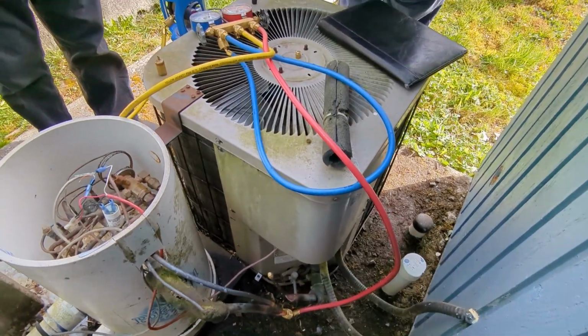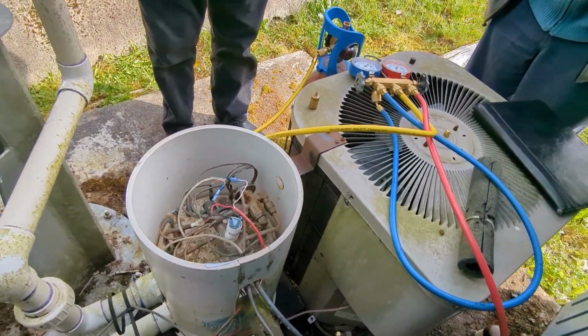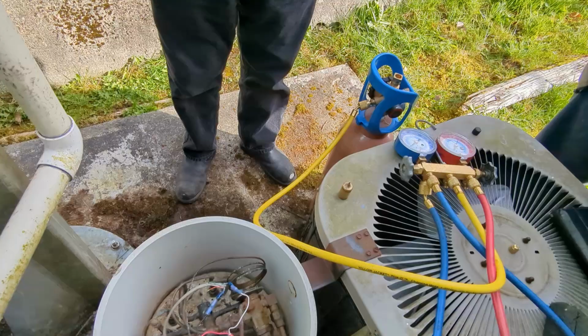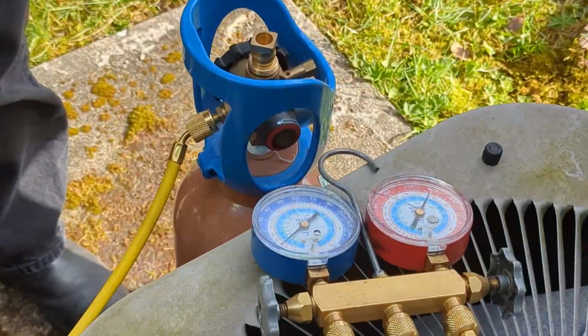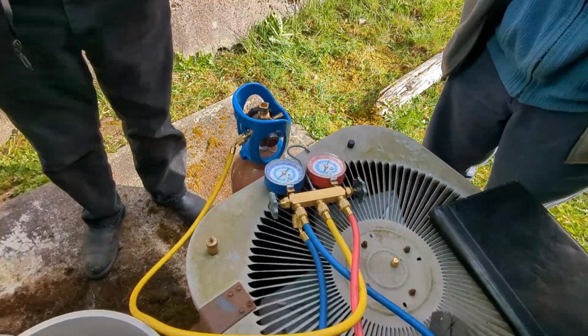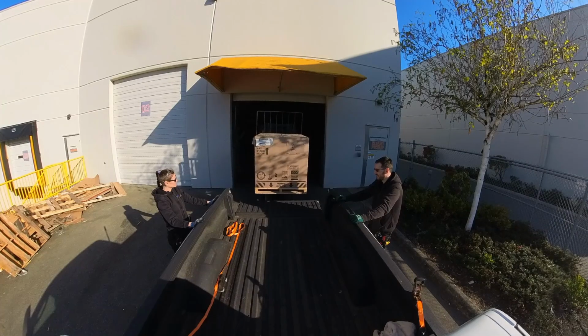All right, we got our nitrogen back out, and we've pressurized this guy back up to 300 psi, and we're gonna leave her again. Fingers crossed. Then we went back on the day to replace the condensing unit and to hopefully figure out if there was a problem with the heat exchanger or not.